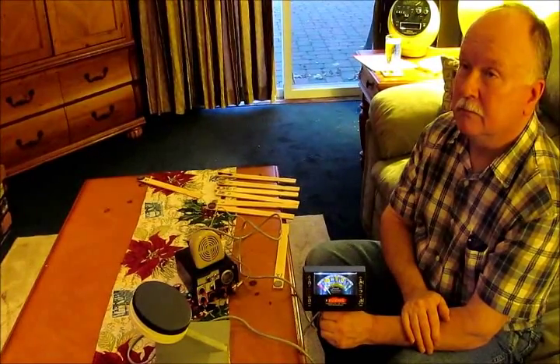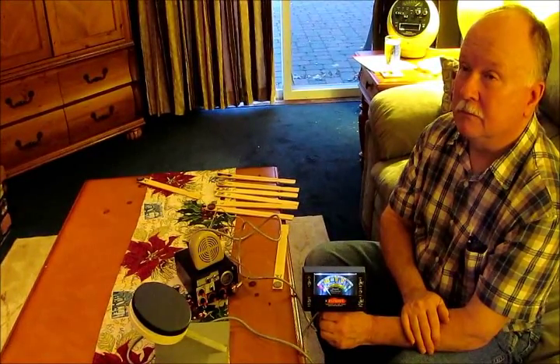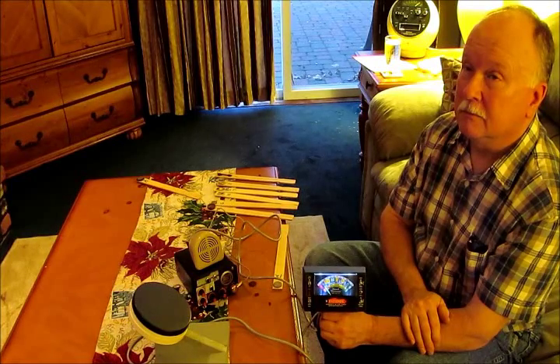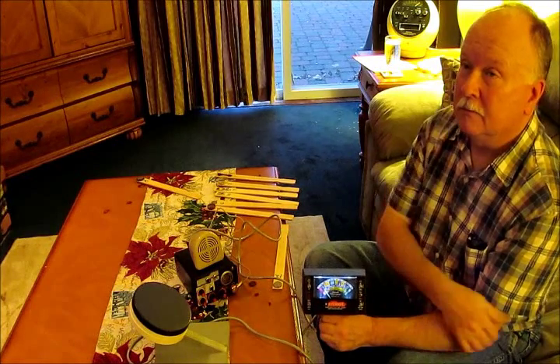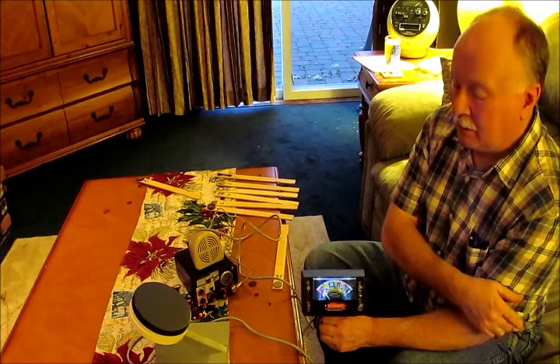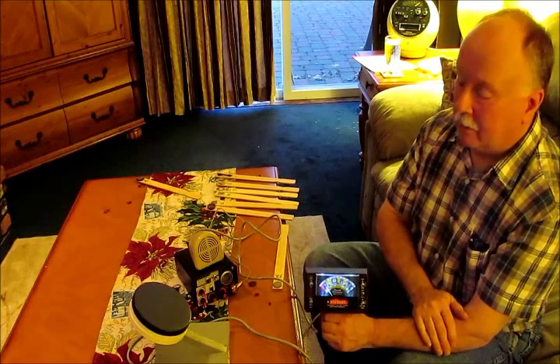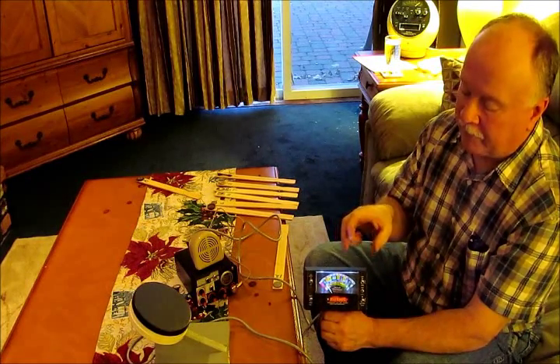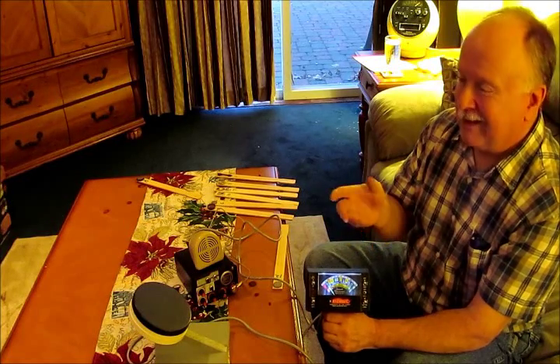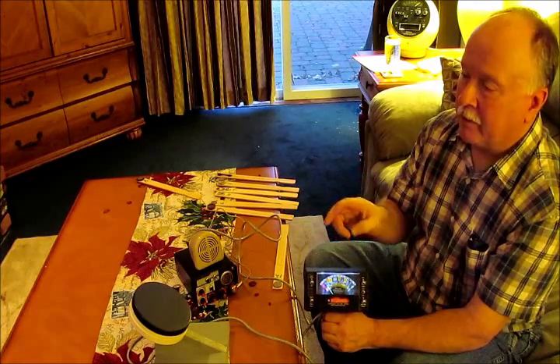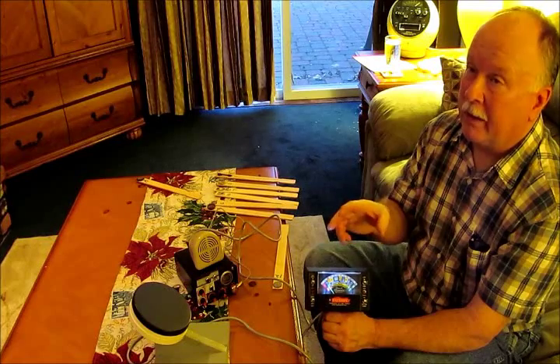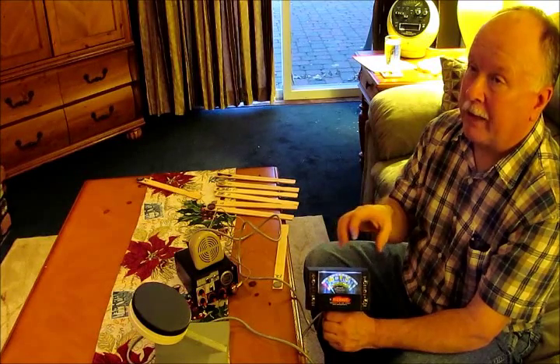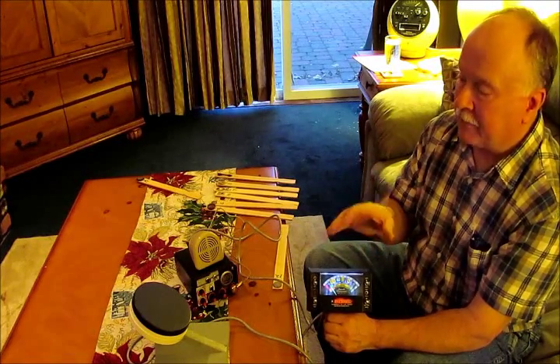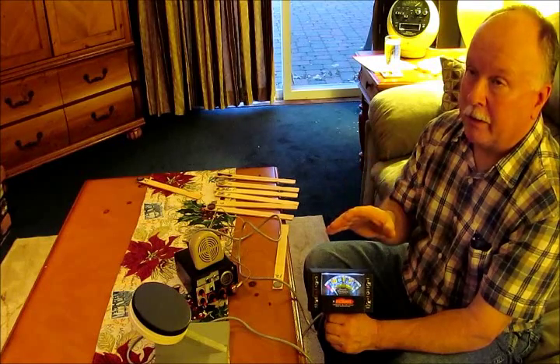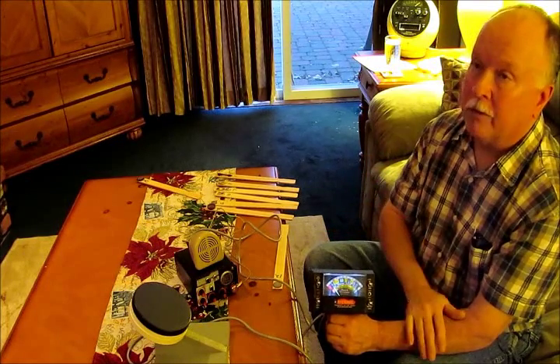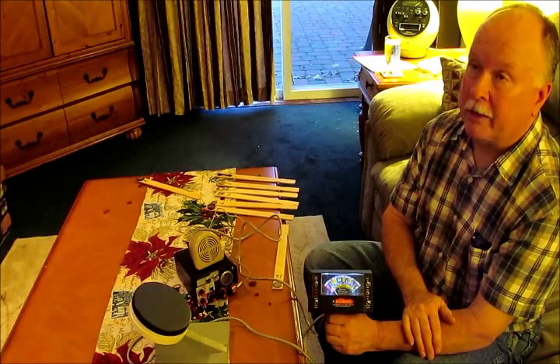Okay, well, Joe, what if you have a target that is a different size than a quarter? Say you have a penny or a dime. How would the meter react? You mean for the calibration? For the calibration. Actually, there's a certain range that's programmed into it. If I remember right, any target between like 175 and 180 will still make it calibrate accurately. But just to be safe, I always recommend using a quarter. And I know if you use a quarter, the calibration will be 100% accurate.